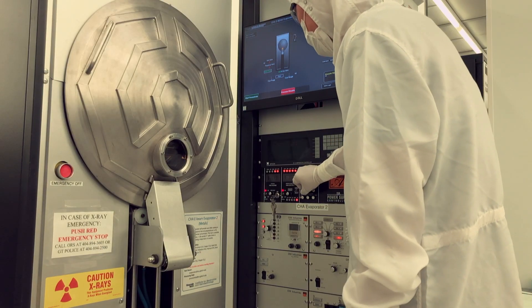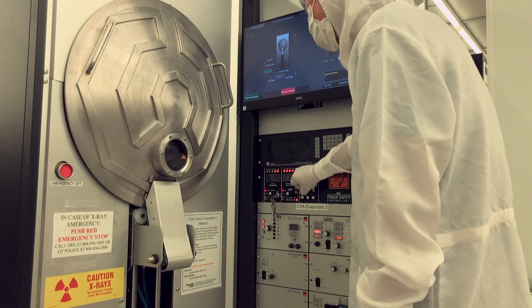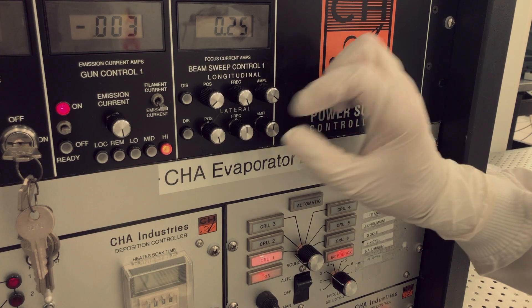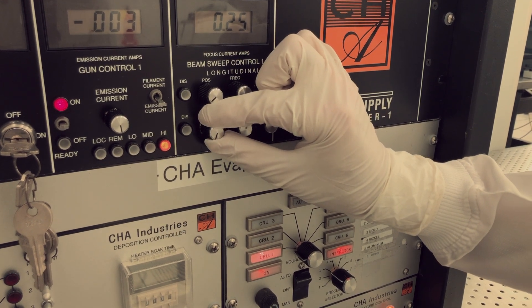The XY sweep controller controls the position of the electron beam. For proper operation, the beam must move in a circle inside the crucible. The beam should not touch the edges of the crucible.